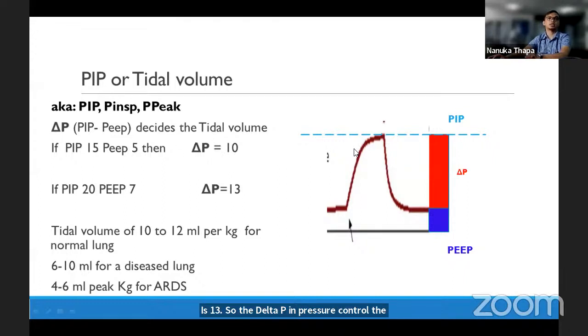Here you can see that in pressure control mode, you can set the delta P or the PIP, and the PIP is constant, and you will get a variable tidal volume. But in tidal volume control, you can set the tidal volume and the PIP. In this graph, you can see the PIP, the upper blue dotted line. This is the peak inspiratory pressure. Above this, the ventilator will not give breaths, will not give pressure above this.